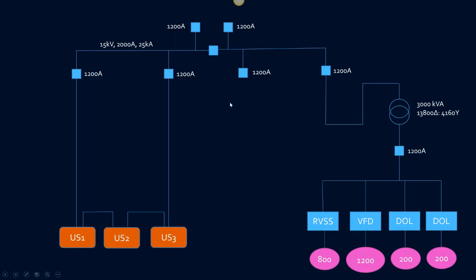Then they're going to feed unit substations over here to the lower right with the medium voltage breakers. And a very popular scheme nowadays is to use two breakers in the medium voltage switchgear to create a loop system. So that's what we've done. And then we have our unit substations daisy chained together. And if you do this, you're also going to require some loop switches on the transformer. And some people call those transformer disconnects. Then you can see over here to the right, we have a transformer.